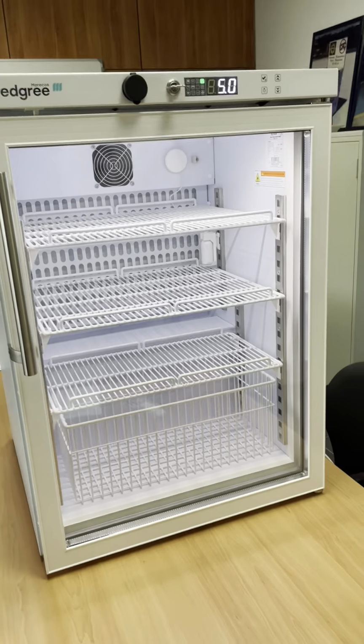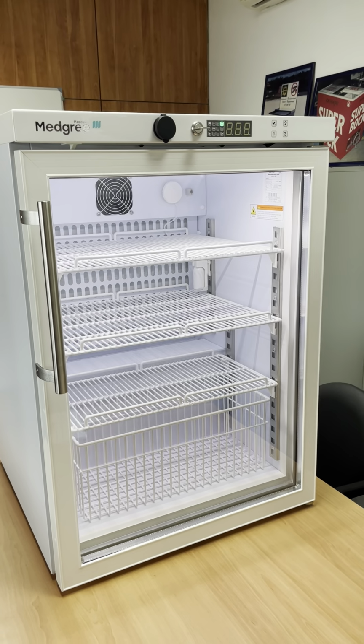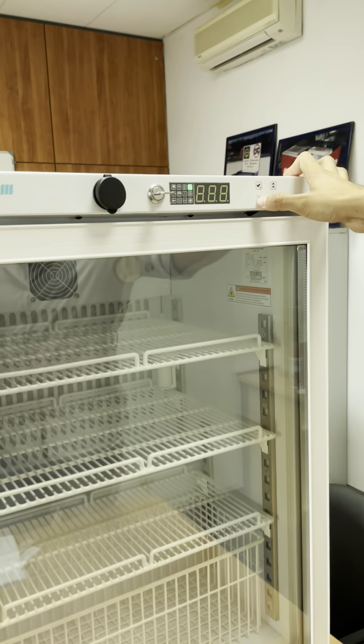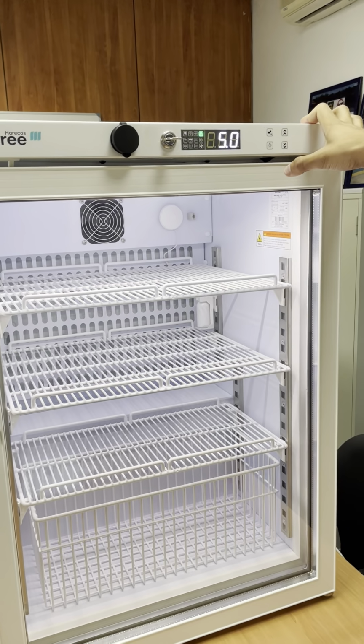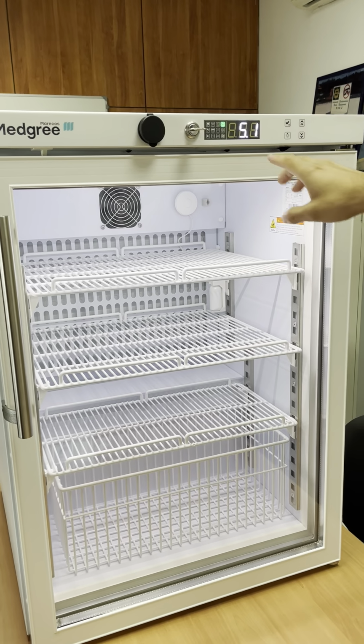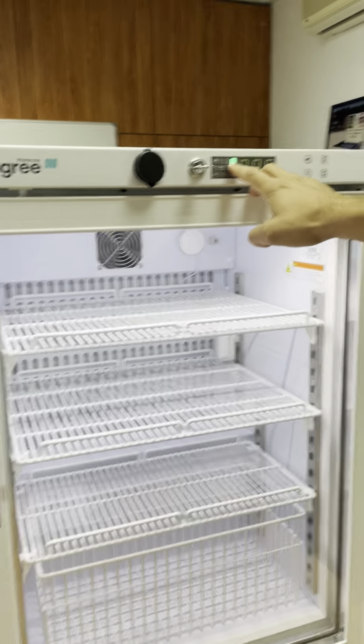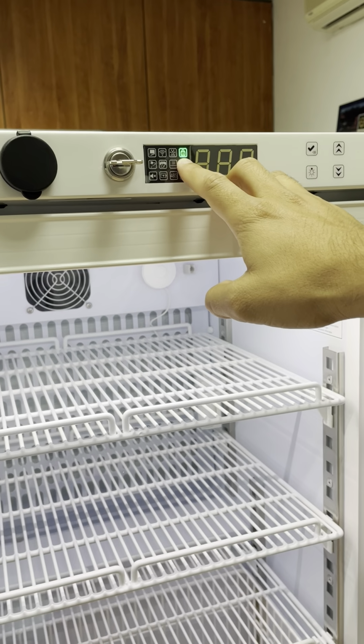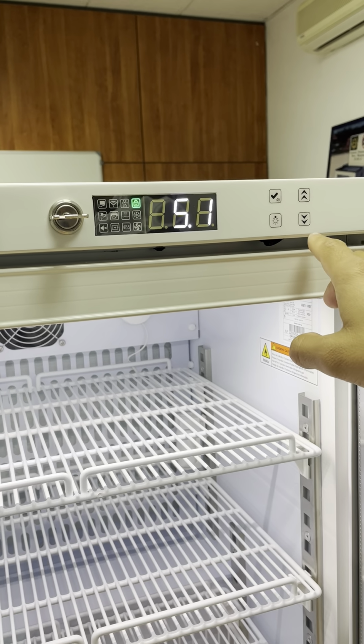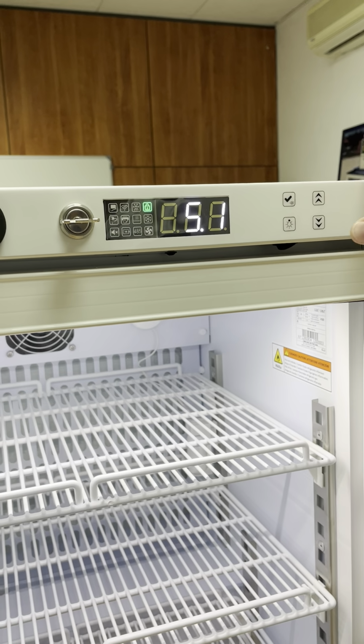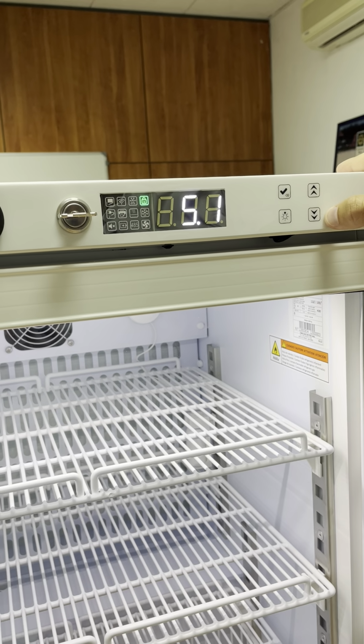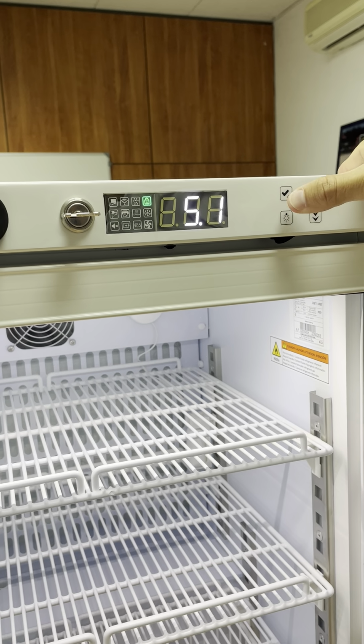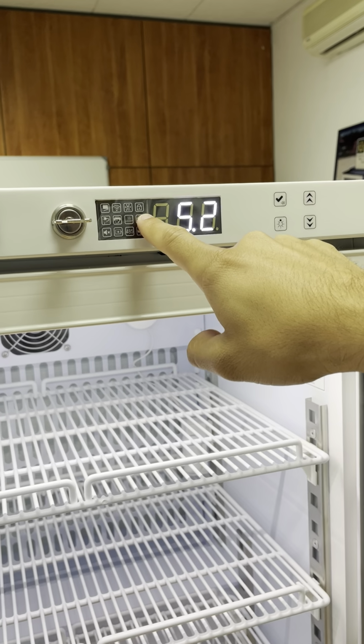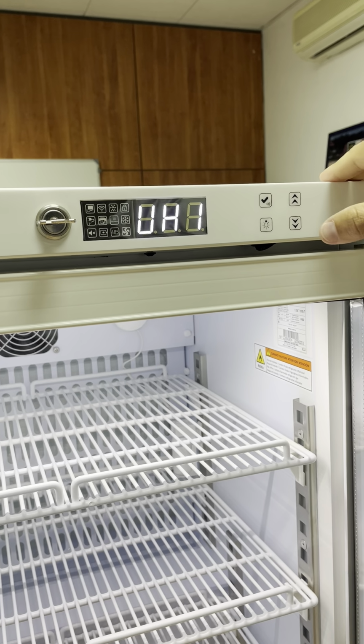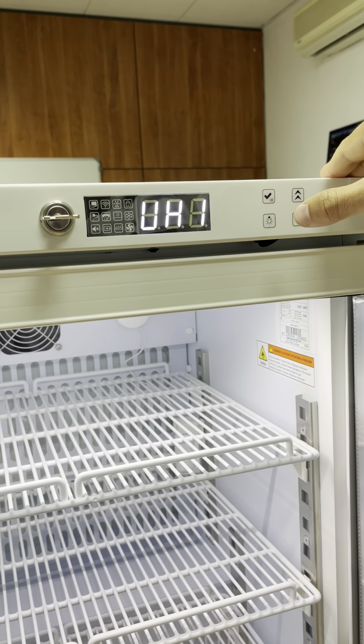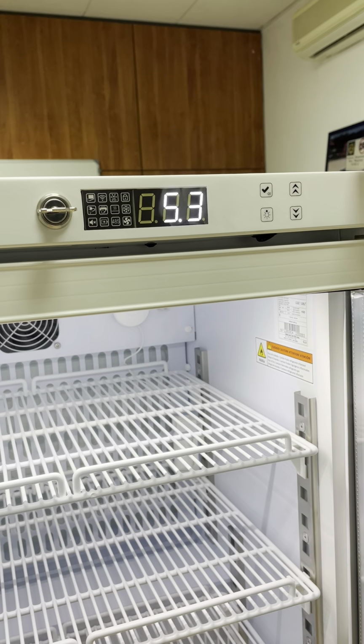So, starting the equipment, you have of course the light button as I showed before. You can switch the light on and off. Then you have the blocked symbol. This means that the control is blocked. You cannot do anything if you touch the buttons. First you need to unblock it. To do this, you click on the below button and then set. And the controller is unlocked. Now you can touch the buttons to enter the parameters or to see what is happening.